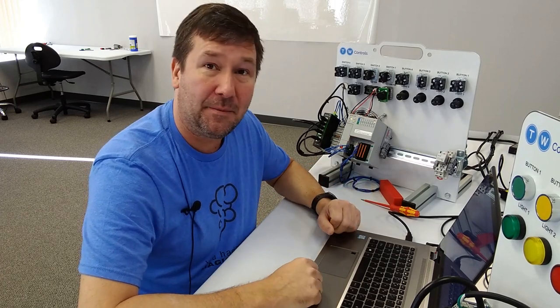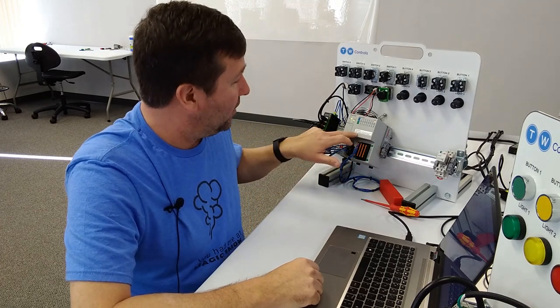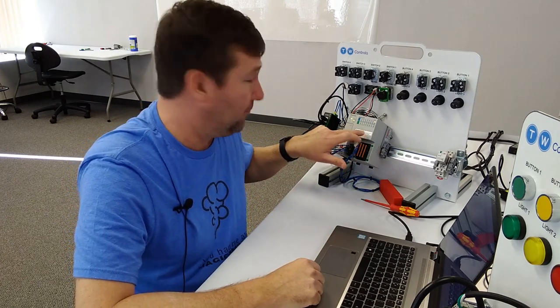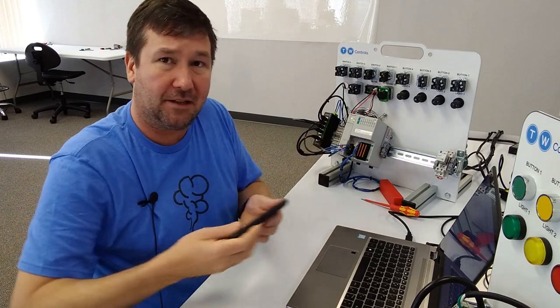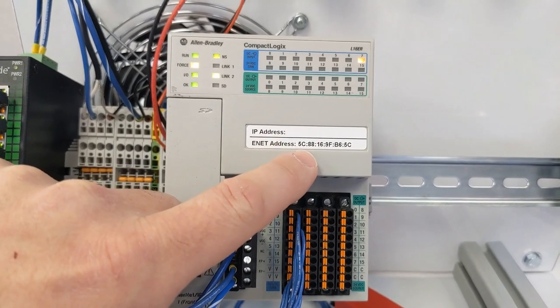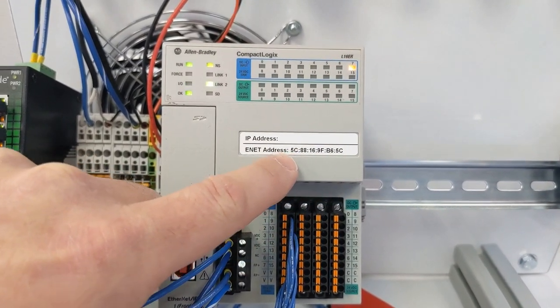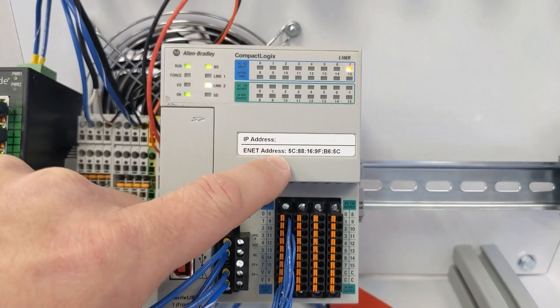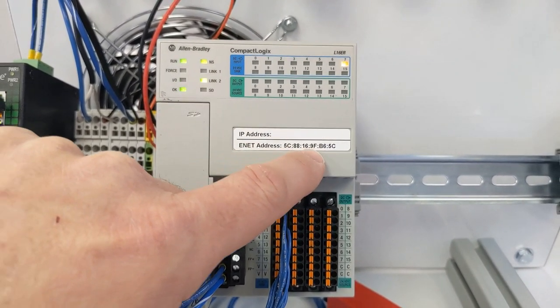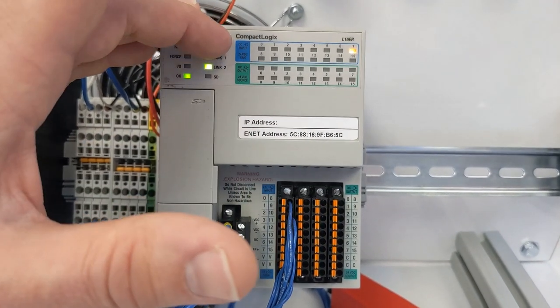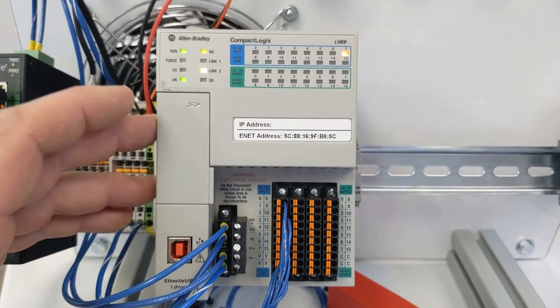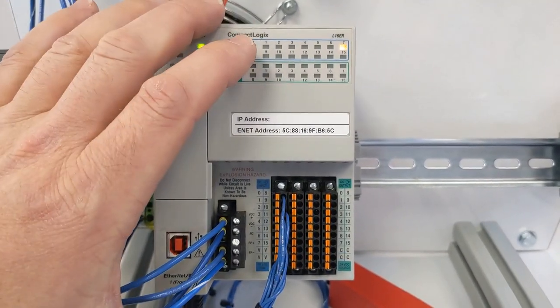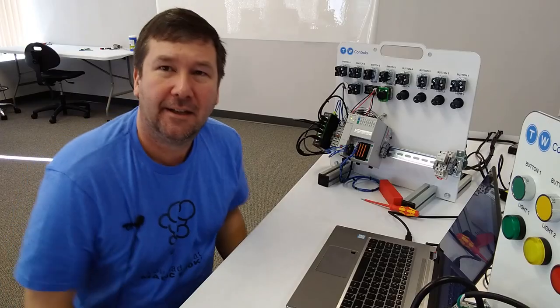Now, on the front of the CompactLogix, we do have the MAC address. And we're very fortunate that they put it right on the front. Let me get a close up of that. Because right here, we have the MAC address. It says ENET address. I don't like that, really. It should say MAC address. But right here, it clearly has this number. And this should be unique to this piece of hardware, not this model. This is like the serial number or the social security number of this specific PLC.